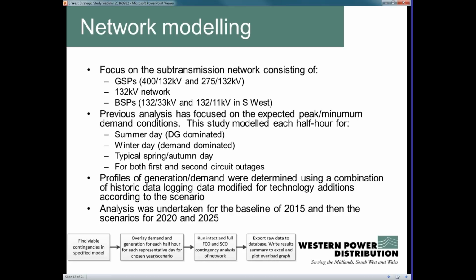We've done that for three representative days, and we've also looked at all the credible first outages - first faults on the network - and then second circuit outage conditions, which essentially looks at where you've got a maintenance outage on the network followed by a fault.